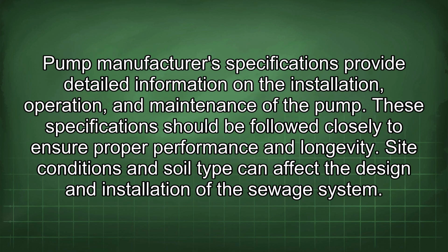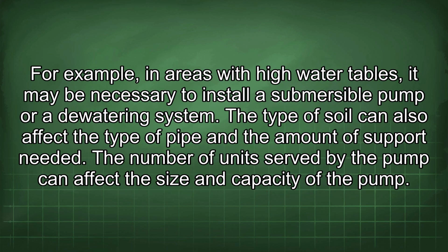Pump manufacturers' specifications provide detailed information on the installation, operation, and maintenance of the pump. These specifications should be followed closely to ensure proper performance and longevity. Site conditions and soil type can affect the design and installation of the sewage system. For example, in areas with high water tables, it may be necessary to install a submersible pump or a dewatering system. The type of soil can also affect the type of pipe and the amount of support needed.